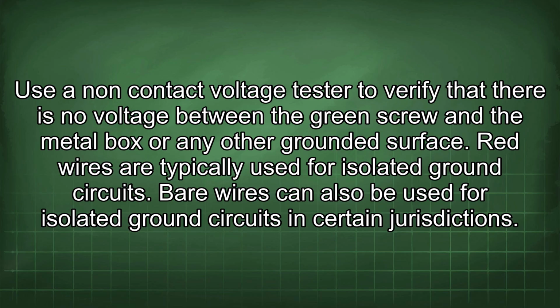Use a non-contact voltage tester to verify that there is no voltage between the green screw and the metal box or any other grounded surface. Red wires are typically used for isolated ground circuits. Bare wires can also be used for isolated ground circuits in certain jurisdictions.